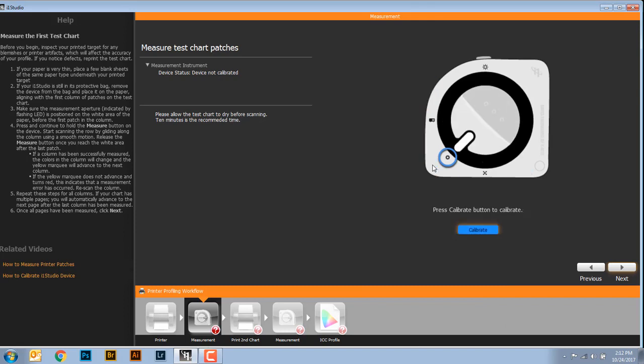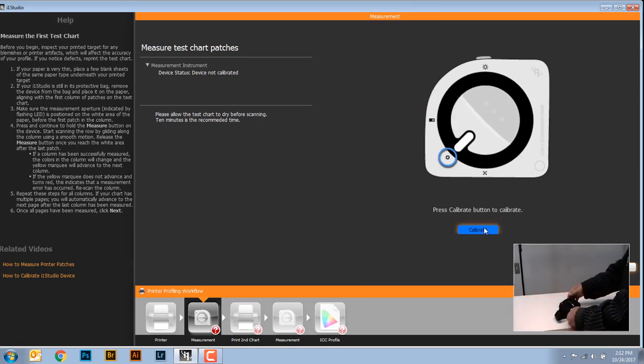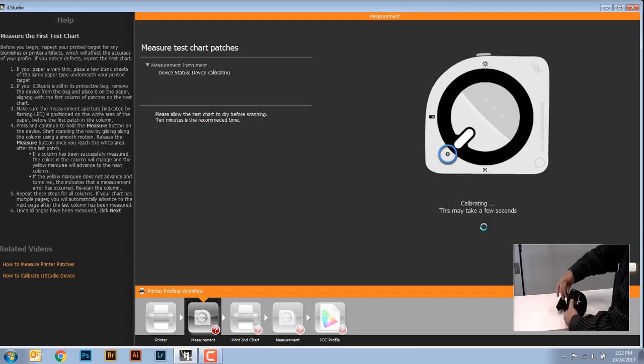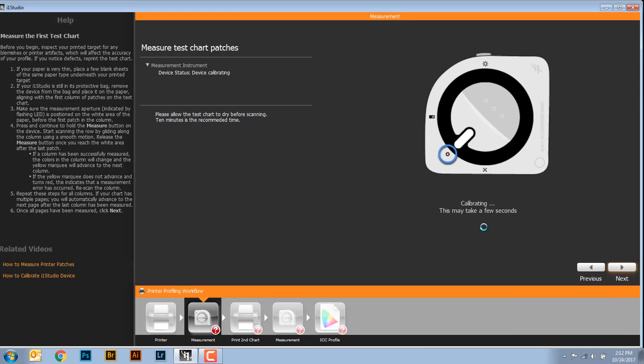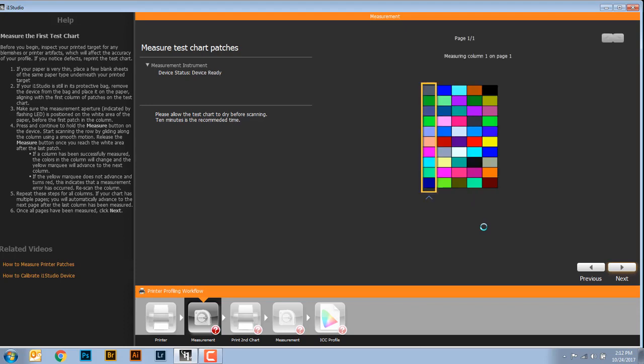So we're going to go ahead and rotate the device into the 7 o'clock position, and now we'll press on the calibrate option, which will send the device into a calibration mode. Once the calibration is finished, your software is going to prompt you once again to move the instrument into the measurement position. And we'll rotate it back to a 6 o'clock position, and now we'll be prompted to print or to measure our printed test chart.